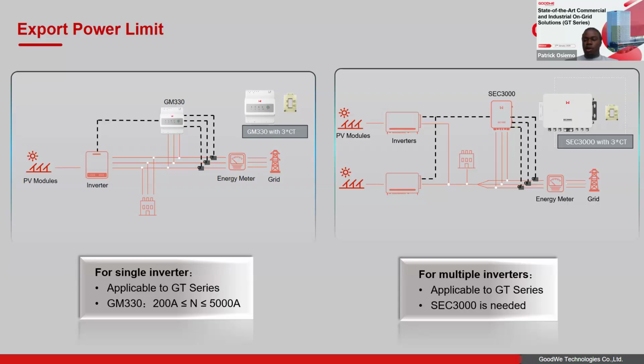Jumping back in, export power limitation is a big topic in the African market. We have two options. You can either connect the GoodWe smart meter, called the GM330, directly to the GT series, and with this function you are able to monitor your grid in the cable. Export power limiting, net power limiting, selling to the grid, all these can be achieved with the GoodWe smart meter and the GT series. If you're doing more than one GT series inverter, then yes, we'll require the SEC3000 control box, and you can do up to 60 inverters in a single plant. So that's the export power limitation.